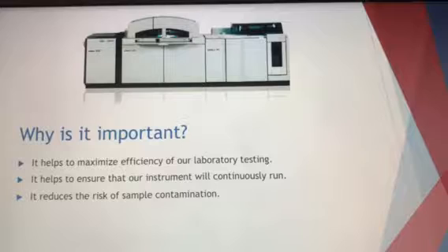So first of all, why is it important that we do our weekly maintenance? We all do our daily maintenance every day, but why is it important to do our weekly maintenance? Our weekly maintenance is just as important as our daily because it helps to maximize our efficiency for our laboratory testing. It helps ensure that our instrument will continuously run and not break down. And I know when they break down, it causes a lot of stress and it causes us to get behind in our patient testing. It also helps reduce the risk of sample contamination, because if we're doing the cleaning that's required of us, it's going to help cut down on that risk that samples could be contaminated.